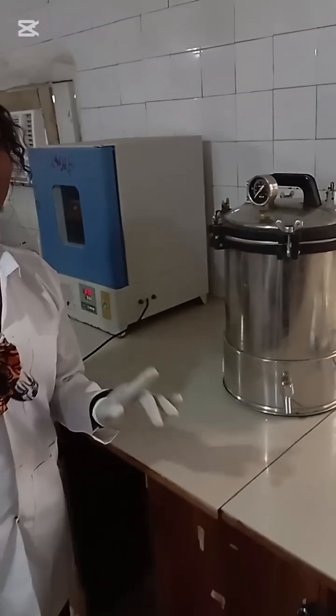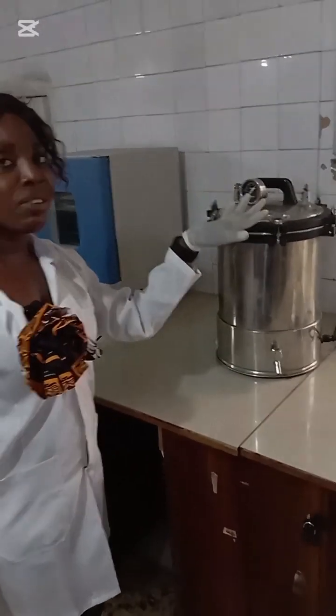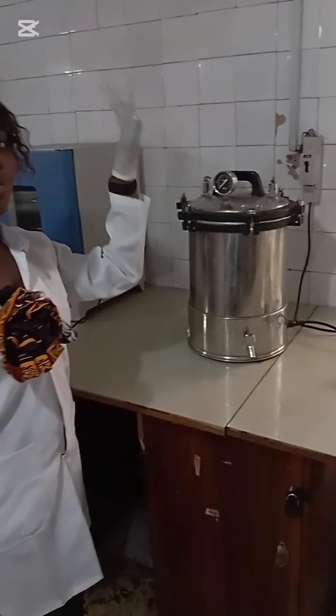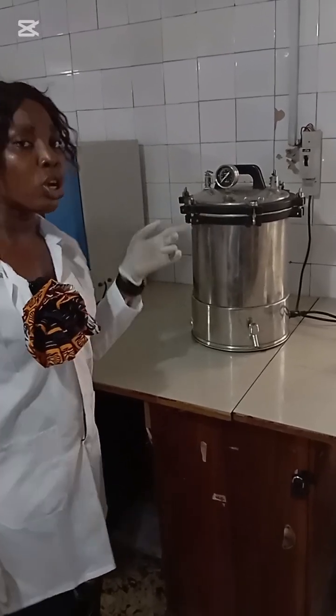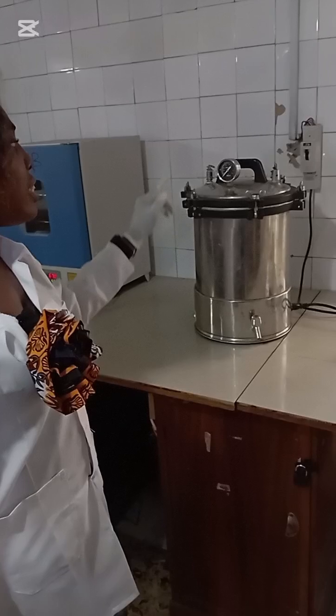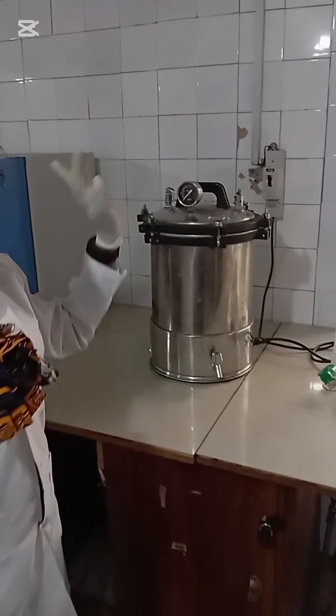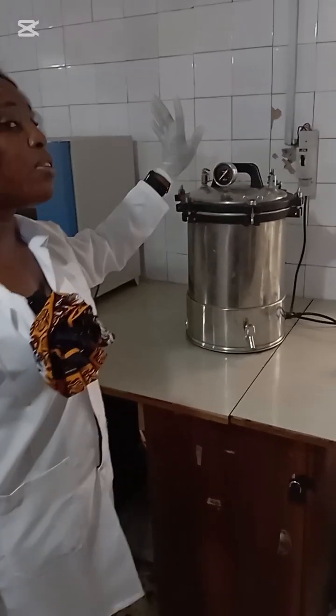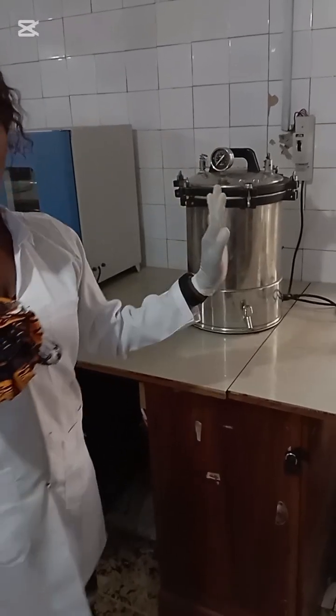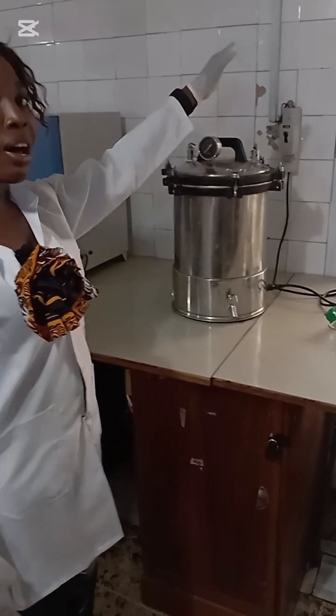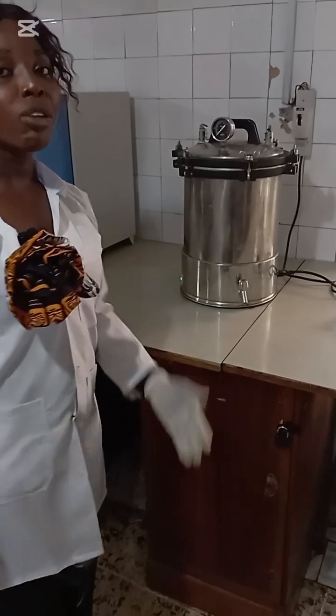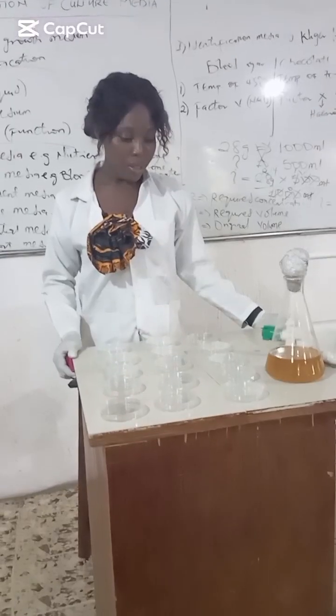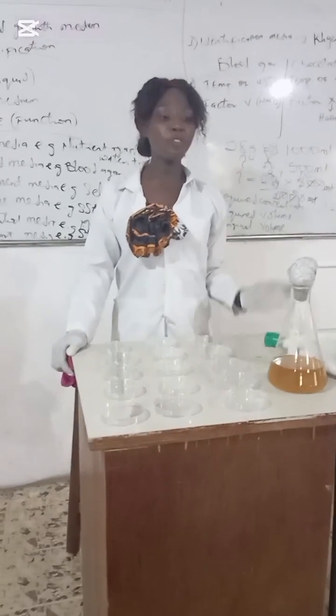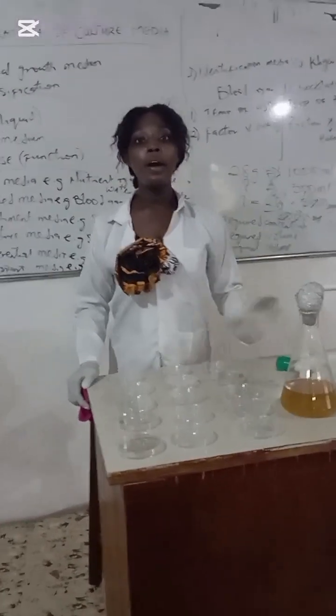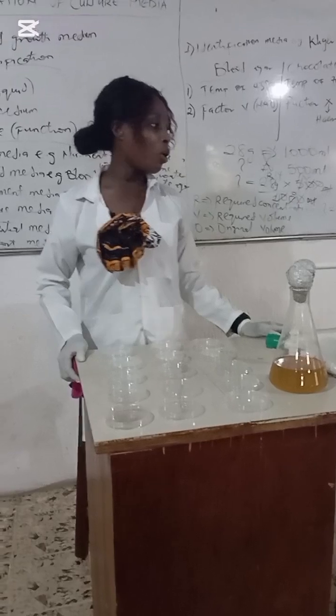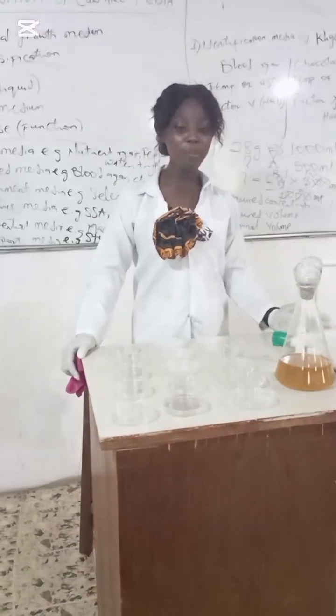It lasts for 15 minutes, after which you put off the autoclave and then you allow it to cool before you open the autoclave. Note, do not open the autoclave when the temperature is still high or when the pressure is still high. You have to allow everything to cool back to zero before you open the valve, and then you open the nut and bring out your item. So our media is ready. We finished autoclaving.